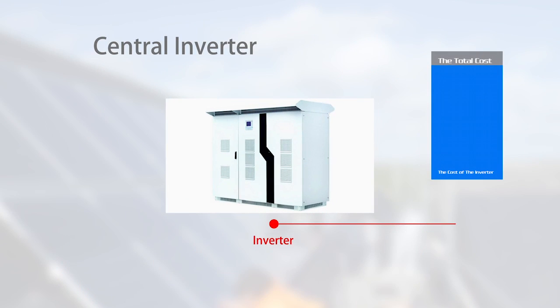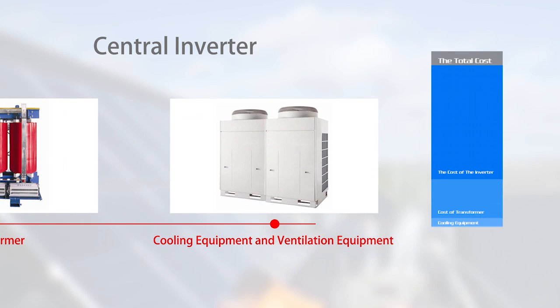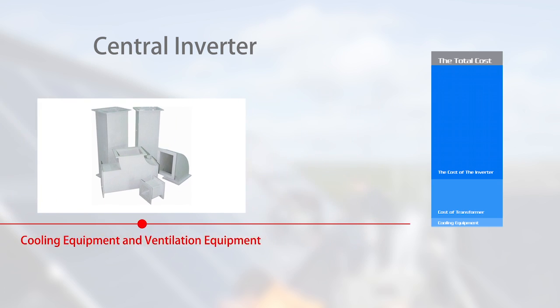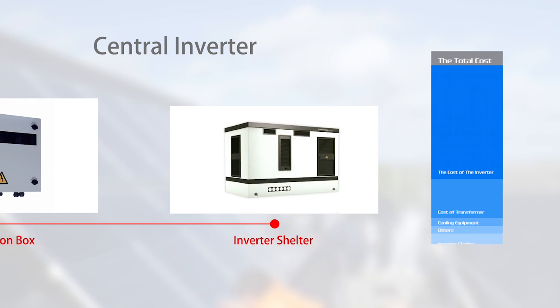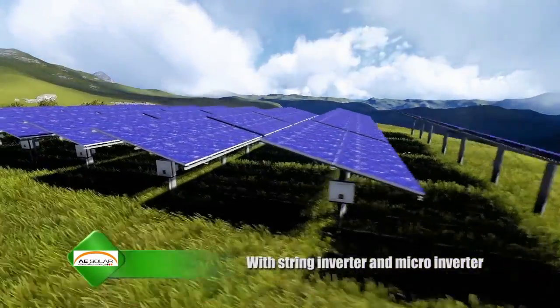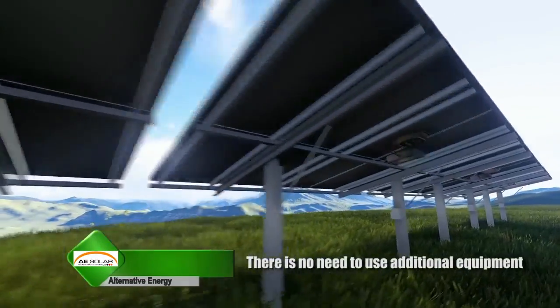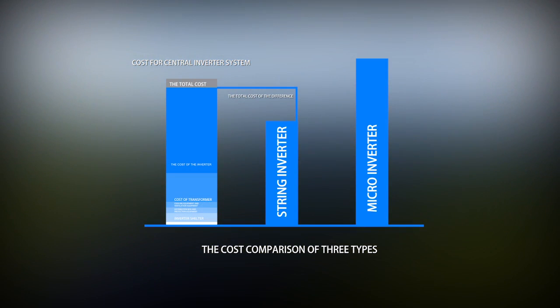System total cost analysis: if you select a central inverter, you will also need to configure a transformer, cooling equipment, ventilation equipment, protection equipment, distribution box, and inverter shelter. With string inverter and microinverter, there is no need for additional equipment. Therefore, though the cost of a central inverter unit is cheaper, you will end up paying more in total additional costs than with a string inverter.